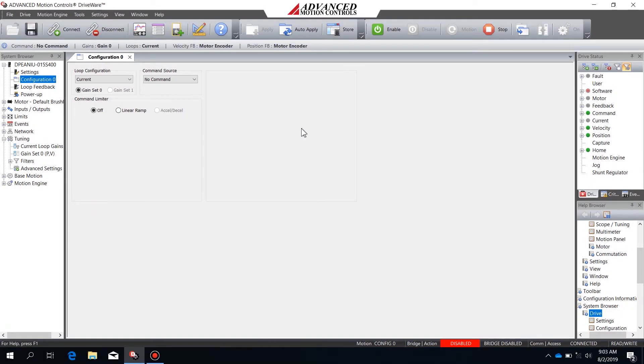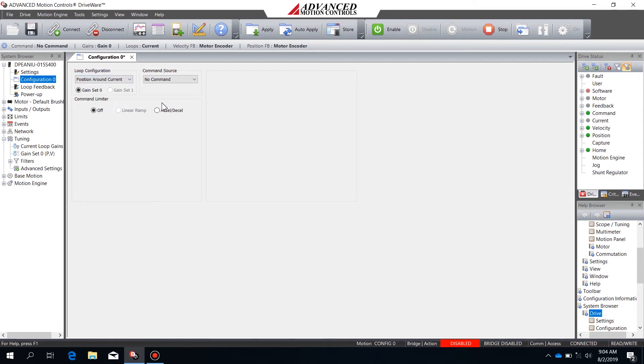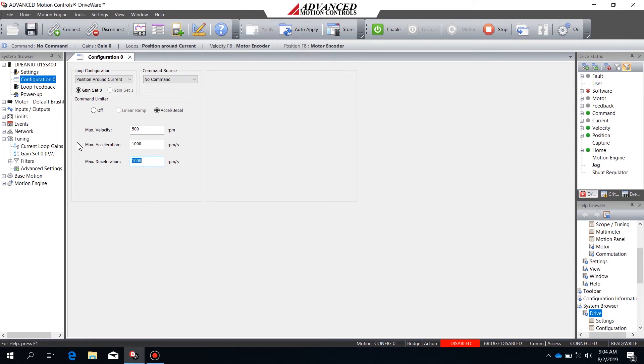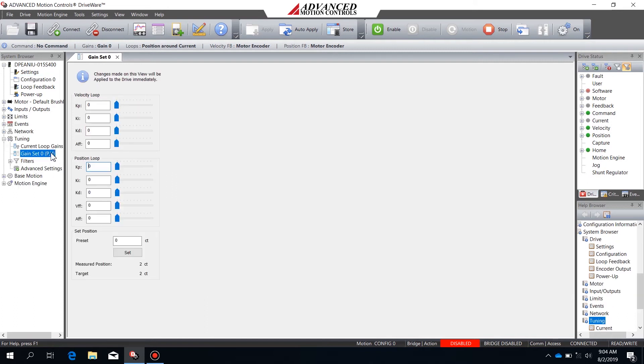Before getting started with position around current tuning, I want to mention a couple things about this mode. It's generally not recommended unless you don't have velocity feedback — for example, when you have an analog position feedback on a brushed motor. In those cases you would not have velocity feedback and would be required to operate in position around current mode. When configuring for this mode, you'll again start in configuration zero, set the loop configuration to position around current, and set the command limiter a little softer so you're not tuning to as aggressive a profile.